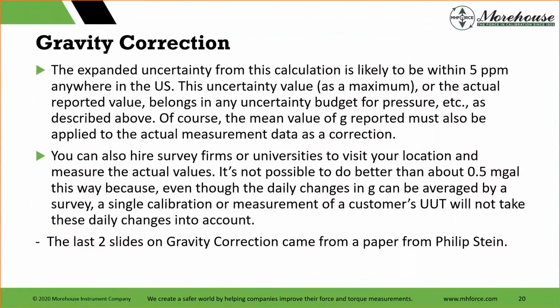The uncertainty value, as the maximum or the actual reported value, belongs in any uncertainty budget for pressure, etc., as described. This one's for torque, so torque budget. Of course, the mean value of G reported must also be applied to the actual measurement data as a correction. So you can use mass and correct, you just have to do it, and you have to know your error sources. You can also hire survey firms, they're going to get you within a half a milligal. Even though the daily changes in G can be averaged by a survey, a single calibration of measurement of customer will not take these daily changes into account. The phase of the moon can affect your gravity. It's so minimal for a lot of these measurements that it doesn't matter.